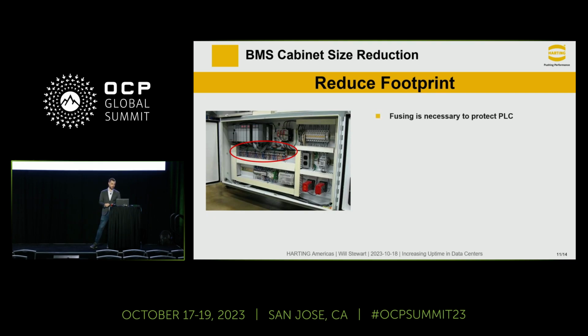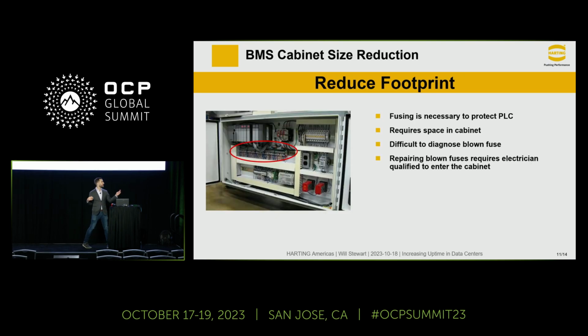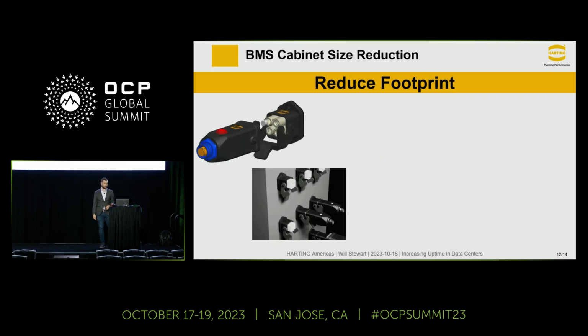One application we have is to improve this system, because if you look at the percentage of the cabinet the fuse terminal block takes up, maybe 10%, it's significant. And it requires you to go into the cabinet to replace the fuse, which means you need labor and the right skill available. What we've produced with one of our co-location partners is an M12 connector that incorporates the fuse, so you can take the fuse out of the cabinet and use it on that M12 on the side, which is especially perfect if you're already incorporating the M12 I talked about before.